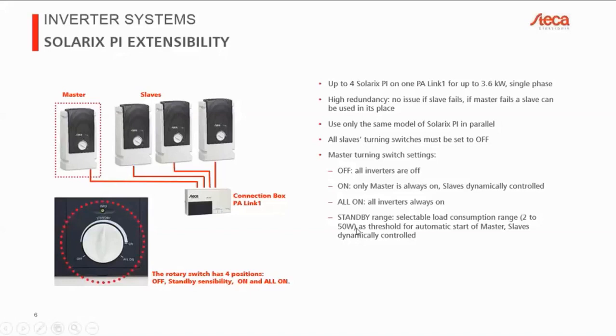Then the final setting is the standby range. So all of this middle range is basically a range from about 2 to 50 watts that you can control, and this is related to the standby function of the inverter. So basically, if you have a house where you need to save as much energy as you can, so you don't want to leave the inverter running all the time, you can set this standby switch so that as soon as you power on your smallest load, the inverter automatically starts up.